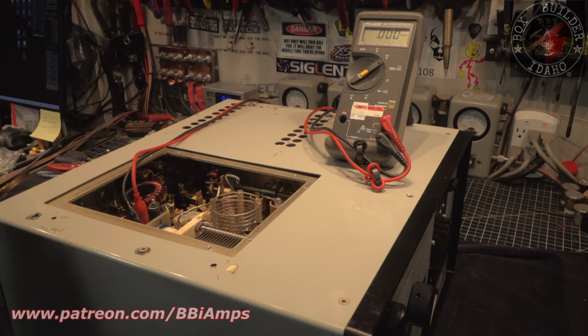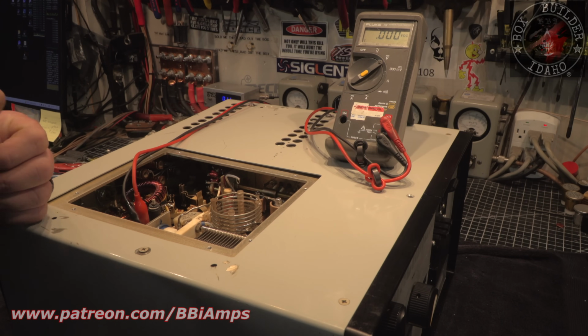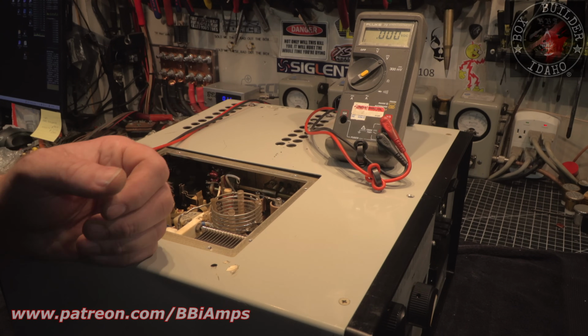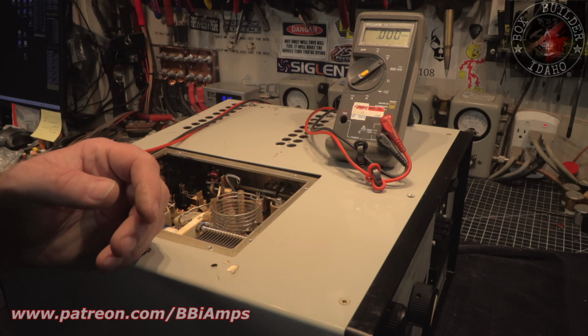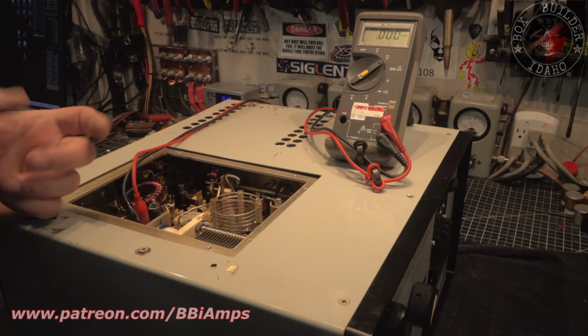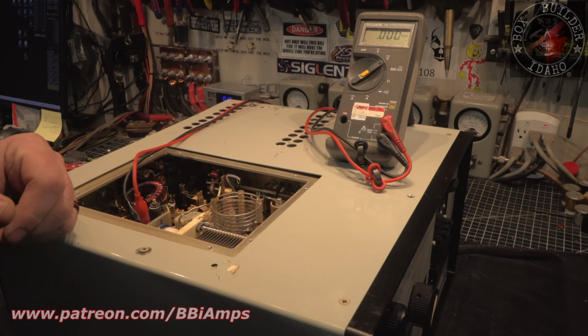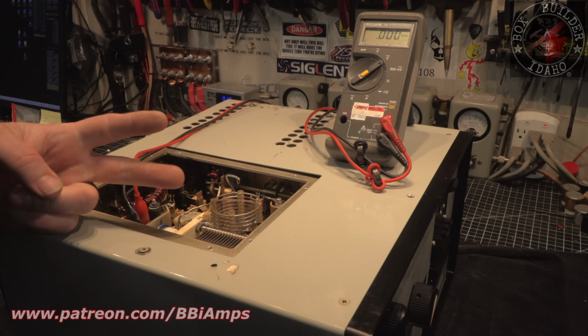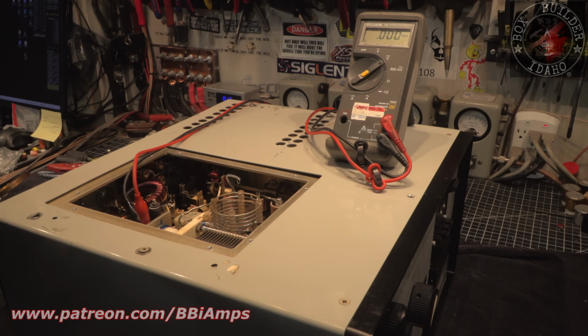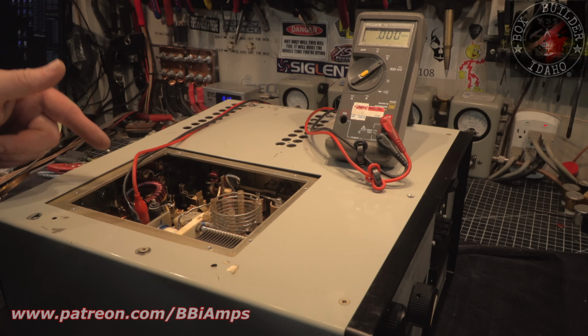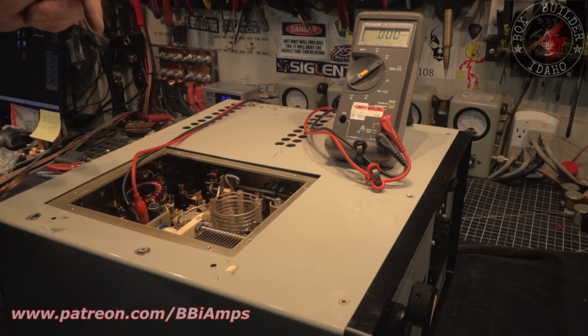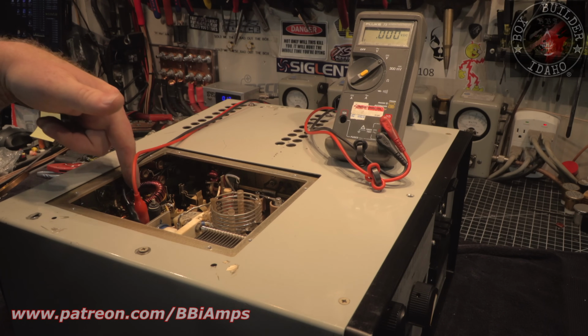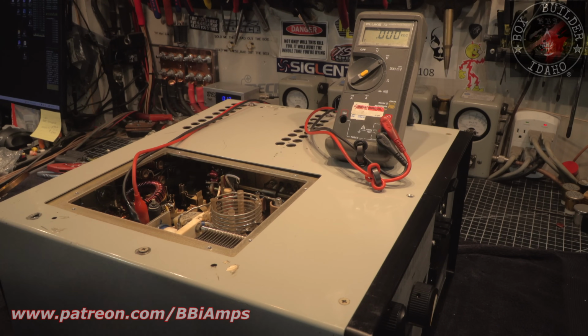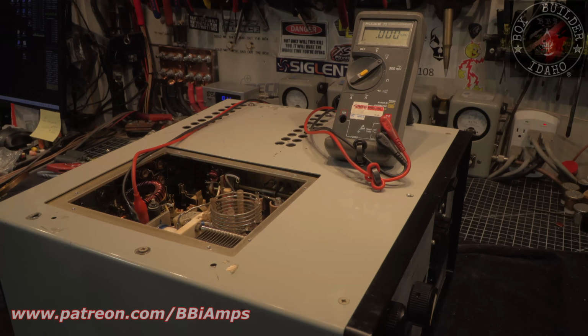Taking into account how expensive the tube is, I'm not going to put the tube in here without letting it sit and cook with just filament and air on it for probably 6 to 8 hours, which is overnight. And then I'll put the high voltage on it, and then we can check for zero signal. So filament volts, power down, and conductivity from here to the disc capacitor, which is going to be right through this coil, is where I'm going to grab it. So let's see what we get.